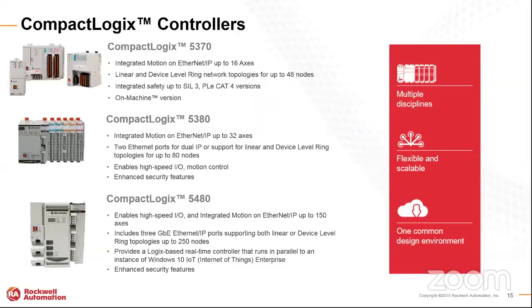Okay. CompactLogix, the L32, any of these, the second generation CompactLogix, which would be the L32Es, the L35Es, those will be going away this year. So that's the platforms below version 20 of 5000. It sort of fits that realm of supporting the older hardware. Those are the versions that still have the serial port on it and only have a single Ethernet port. So you'll start seeing notifications go out. We usually give you guys 2 years' notice, and I think the official date is sometime in 2020. It's December 2020. The letter is out and I do have a copy.